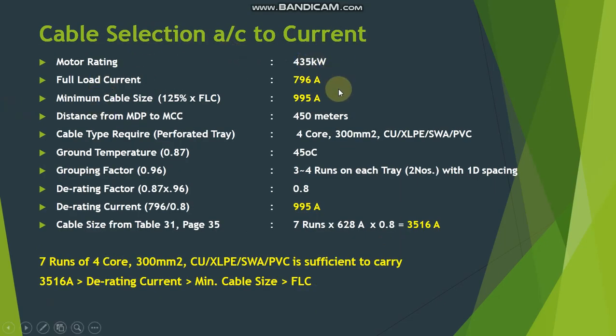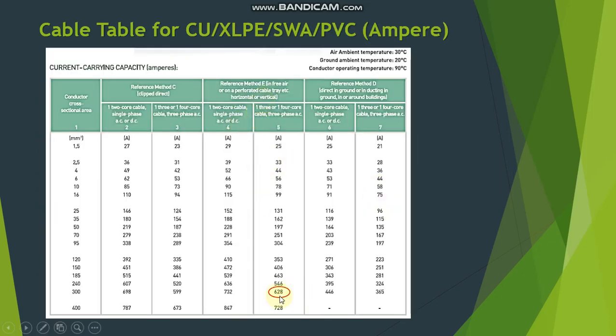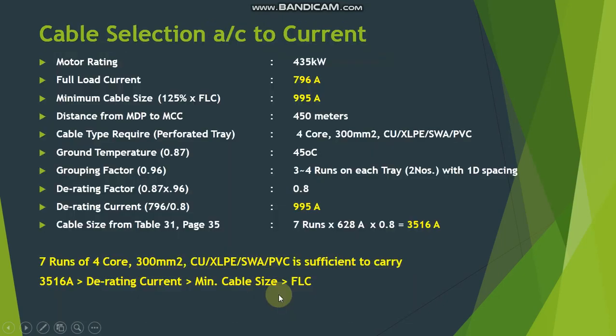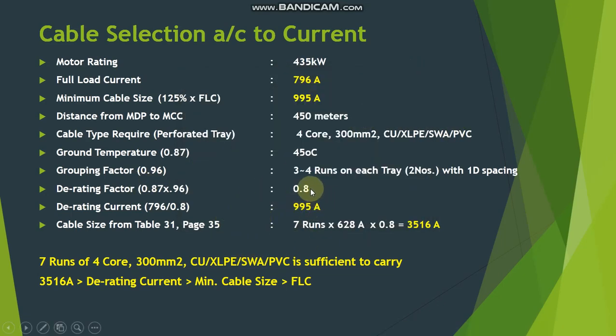Finally, we verify cable selection according to current. Using seven runs of 4-core 300mm² cable, from the cable table the current rating for a 4-core 300mm² cable is 628 amperes. Multiplying 628 × 7 runs × 0.8 derating factor gives 3516 amperes, which is greater than the derating current of 995 amperes and also greater than the full load current of 796 amperes. Therefore, 4-core 300mm² copper XLPE armored cable is absolutely suitable under these conditions.